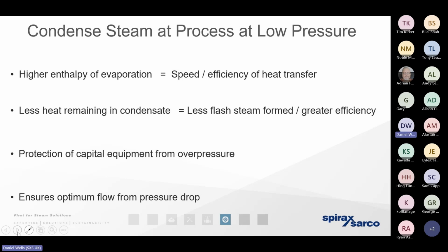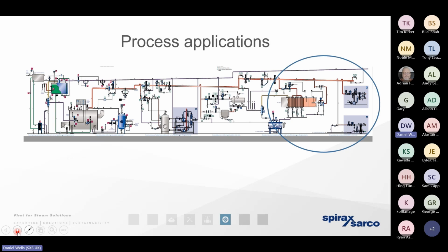Now, by generating and distributing steam at high pressure and then reducing the pressure, yes, it means we're protecting the capital equipment from overpressure, and it means we can move the steam very, very quickly in a small infrastructure. But we also know that there's actually more useful heat energy present within steam at a lower pressure than there is at a higher pressure. So we've got a significant benefit there for heat exchange purposes. So we need to bear that in mind when we get the steam to the point of use.